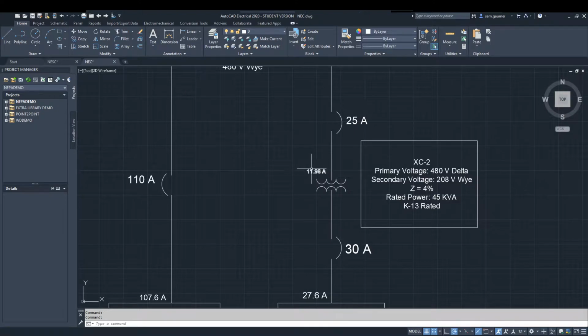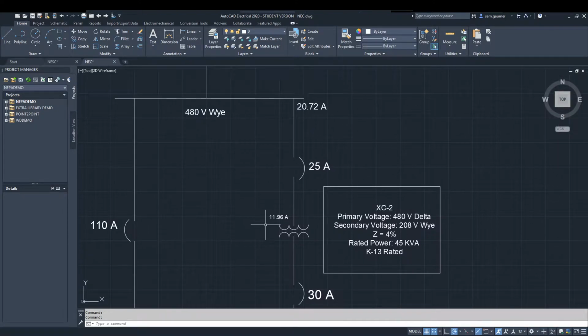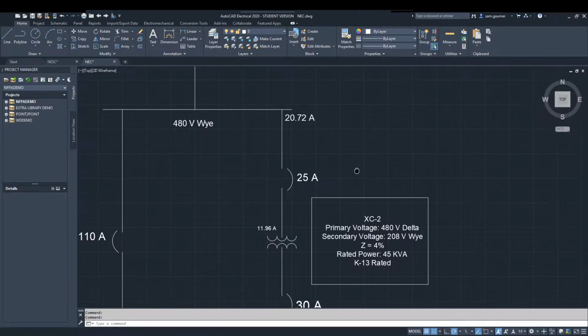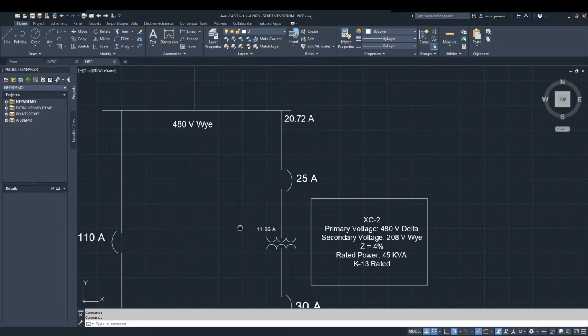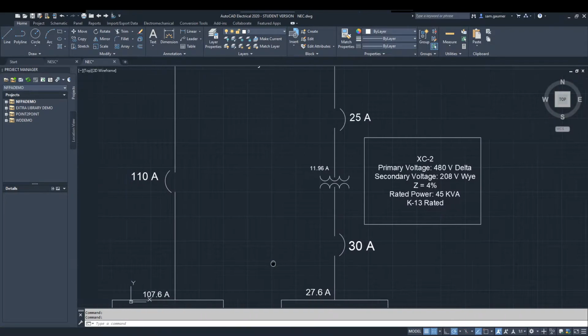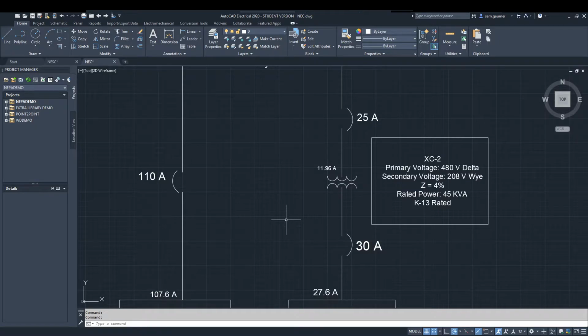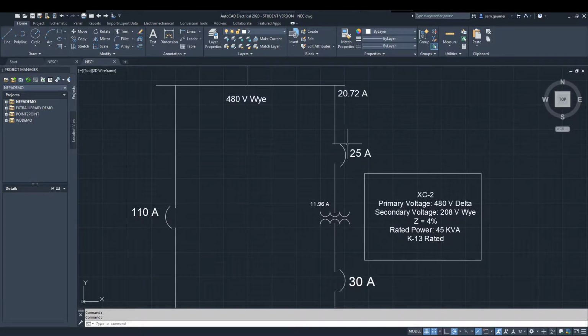That means the current on this side is going to be lower. But we have to remember this is a delta, so when it goes to the line, it has to be changed to a Y. So it's going to go from around 12 amps to 20.72 amps. Based on that 20.72, the 27.6, and the 107.6, that's how I determined these circuit breaker values.